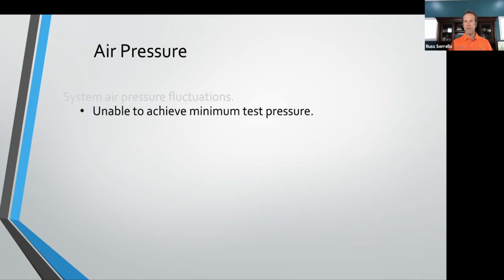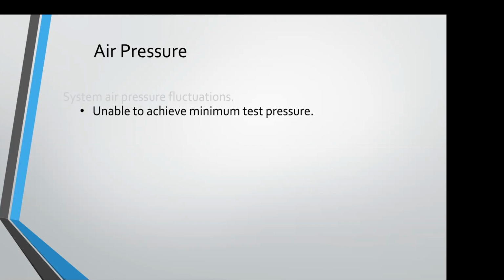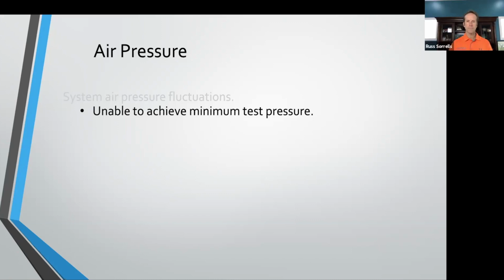So as an example, if you have a 50 PSI test pressure, I would typically set it at 52 and 48, depending on the application. There's not a scientific method that I'm aware of in setting the upper and lower limits. Anything to add to that, or any method to a madness on that one, Gordon? You could say 10%. Yeah, that would be a starting point. And then if you've got certain tolerances that you need to meet within your testing, which we do see, 50 PSI plus or minus 2 PSI in your case, 48 and 52, that would be the right way to set for that.